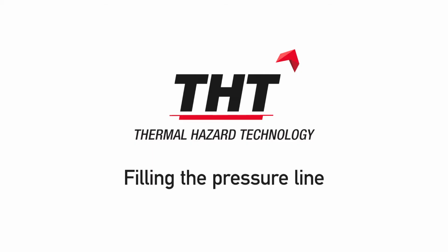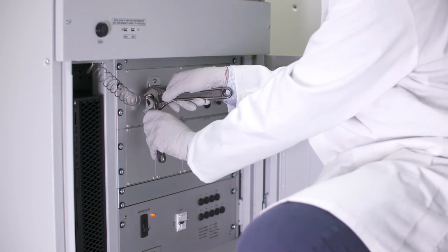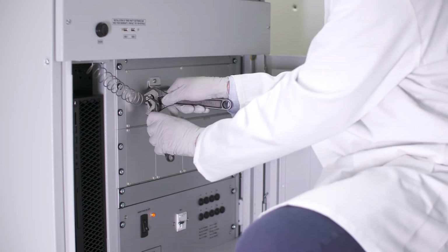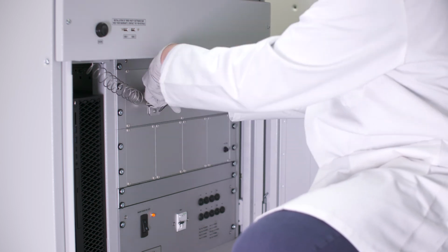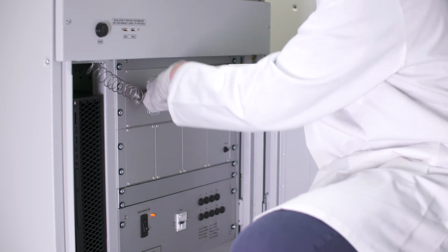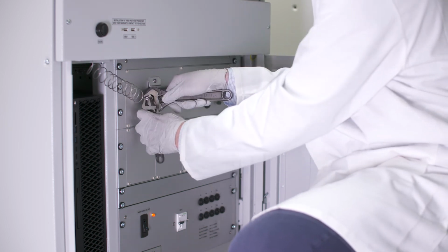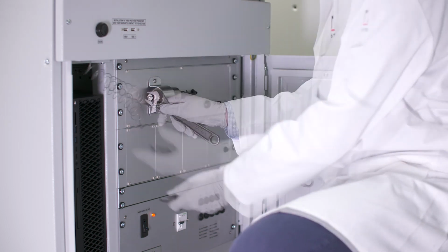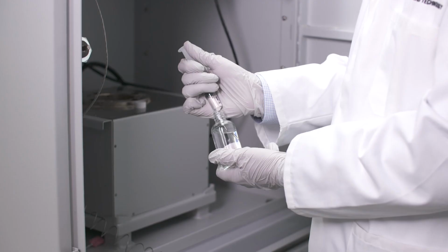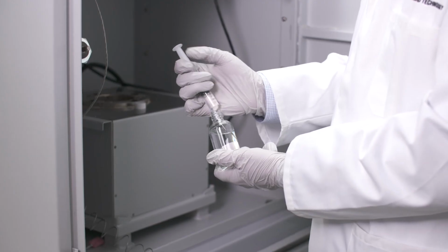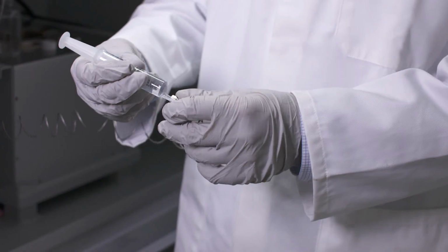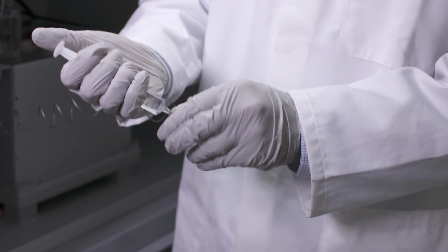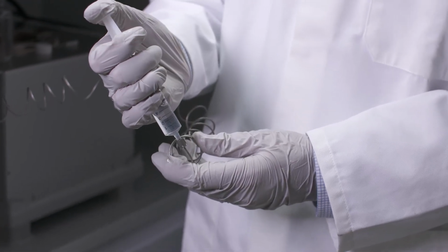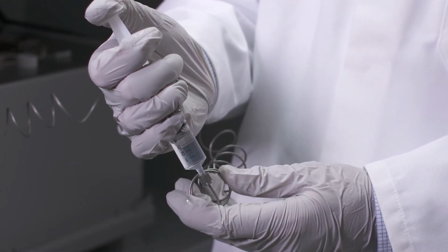Filling the pressure line. After several tests, it's a good idea to replace the oil in the pressure line. To do this, first uncouple the lower part of the pressure line from the transducer. Then fill a syringe with silicone oil and attach it to the top part of the pressure line. Press the syringe for about a minute until oil drips out of the lower end of the line.